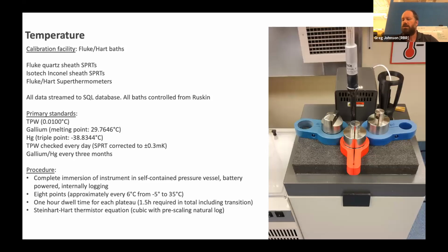There are 2 designs that are typically used in this kind of section of the ITS 90 temperature scale. One is using a quartz sheath. Most of our quartz sheath ones are Fluke. And then we have a couple of Inconel sheath. Inconel is a nickel-based superalloy, typically used in aerospace applications. And it's also very stable over time. And stability is the game with an SPRT because you don't want anything to be drifting. You don't want any mechanical stresses. You don't want any strain buildup.